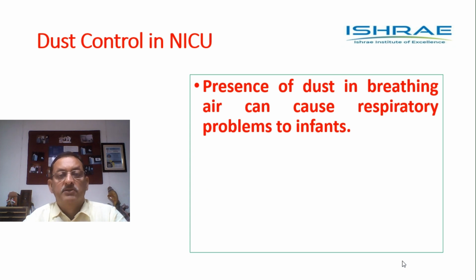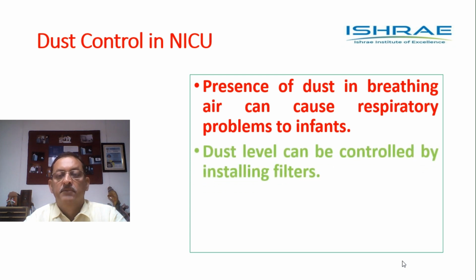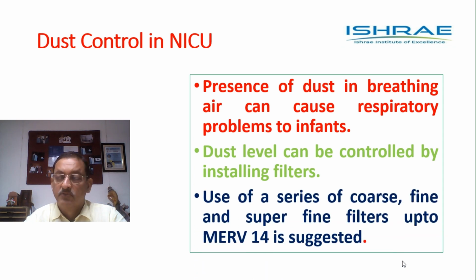Dust control in a NICU. Presence of dust in breathing air can cause respiratory problems for infants. Dust level can be controlled by installing filters. What size of filters? What kind of filters? Well, for different needs, the requirement of filters could be different. However, a series of coarse filter, fine filter, and superfine filters up to MERV 14 is suggested for this purpose.